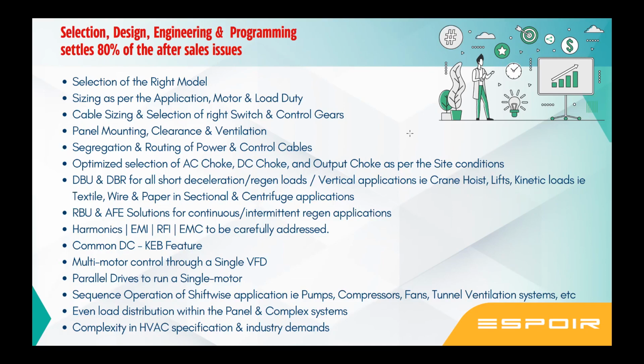Sequence operation of equipment, utility equipment. For example, in pumps, you have three pumps. One pump is always on standby. What if you don't use the pump for more than a week? It gets jammed. So you need to sequentially use pump one, pump two, pump three. Whatever is available on standby is used the second time, and the third time would work on standby. So it is like a sequence. Every 8 hours you can change that.